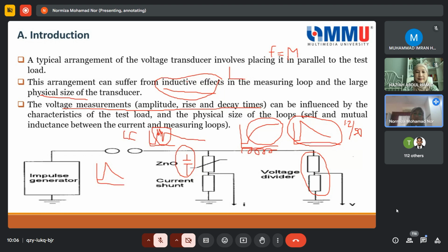When it is in megahertz, the inductive effect, the formula is X = 2 pi F L. So the inductive effect becomes higher because your frequency is high, in the megahertz range. For this reason, the inductive effect is one of the determinant factors in deciding whether your measurement is correct, reliable measurement. So this has to be reduced or minimized. In order to reduce that, there are certain ways. One way is you get to know it from the calibration, and then of course minimize the loop in the circuit, or the physical size of the transducers.